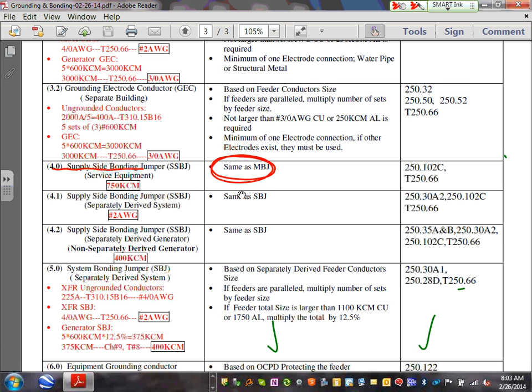Do you guys see the terminology that they use? Supply side bonding jumper. You size it exactly the same as the main bonding jumper. Identical to the main bonding jumper. Can I have thumbs up, Chad? We know the supply side bonding jumper. So when you become a project manager, guys, that's the thing they're going to be looking at. Your conductors are coming. The inspector will come and say, well, you didn't bond your conduits.